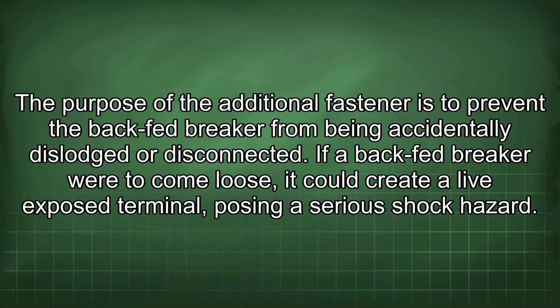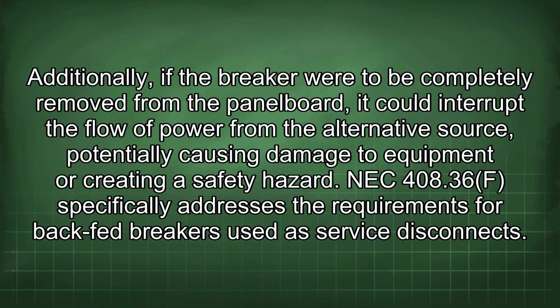The purpose of the additional fastener is to prevent the backfed breaker from being accidentally dislodged or disconnected. If a backfed breaker were to come loose, it could create a live exposed terminal, posing a serious shock hazard. Additionally, if the breaker were to be completely removed from the panel board, it could interrupt the flow of power from the alternative source, potentially causing damage to equipment or creating a safety hazard.